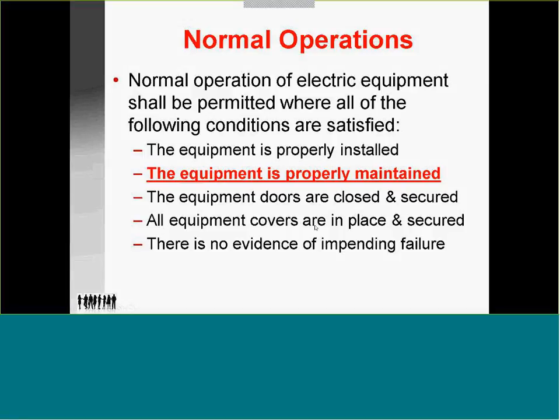It was added that all equipment covers are in place and secured. If the cover on a breaker panel has 6 screw openings, 6 screws must be used to put it back together. This ensures the panel will hold up in any arc flash event. There's no evidence of impending failure. What's that? Impending failure would be discoloration, heat, insulation cracking from the heat. It's easily seen in many incidents, and I'll show you one here shortly. But then smoke is one of the most obvious, and if it's already caught fire, I think you're very aware that the failure is in progress.